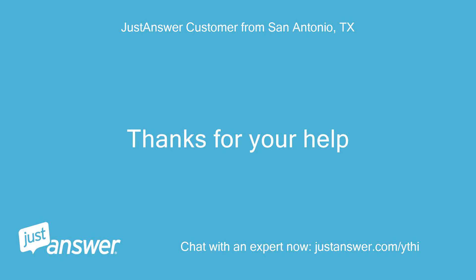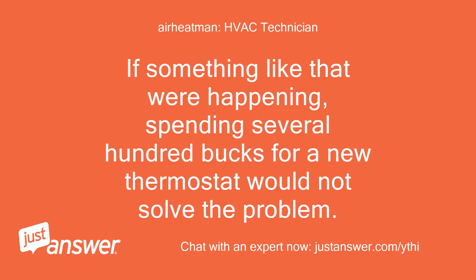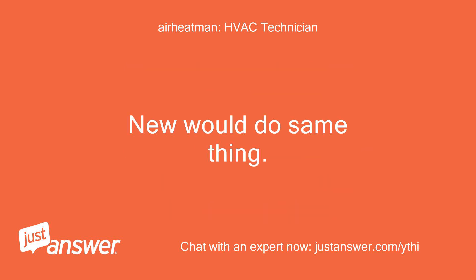Thanks for your help. I was curious about the exact issue you were having with the screen, because if it goes blank on occasion, the issue may be a float switch breaking power, and as water drains out it resets. If something like that were happening, spending several hundred dollars for a new thermostat would not solve the problem — the new one would do the same thing.